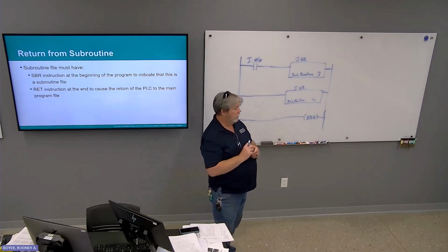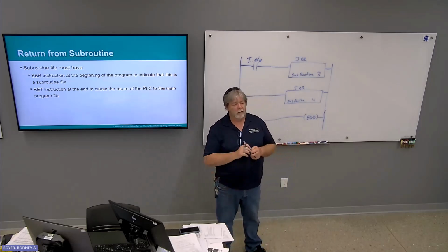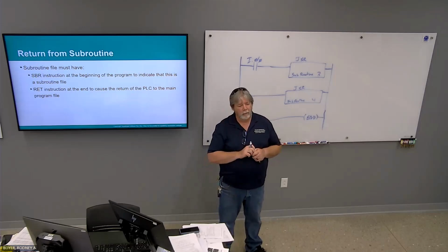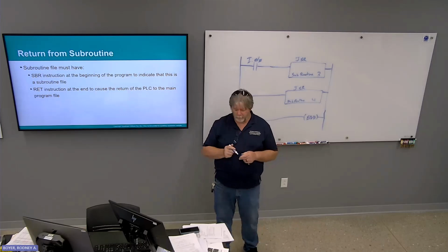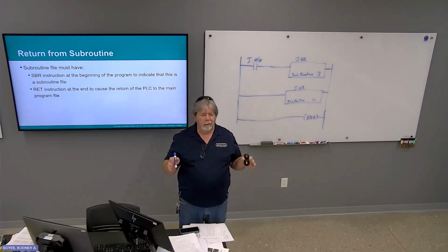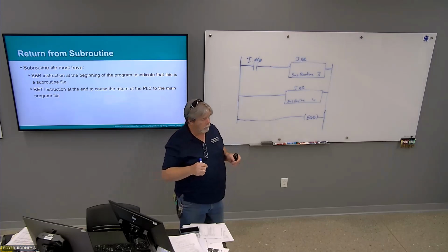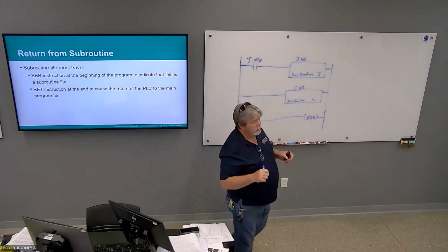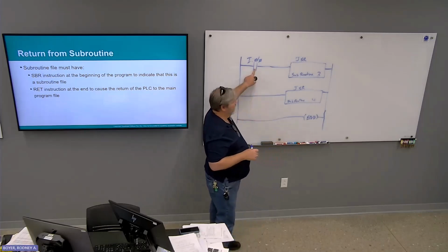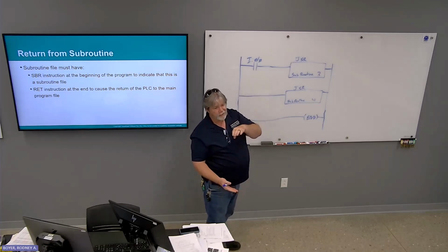One of the cool things about the return instruction, though, is that it does not have to live at the end of your program. So if you need to adjust the pressure inside a vessel of some sort, and you're doing it by modulating valves or controlling fan speed or whatever, when you need to make an adjustment, you turn off your conditional logic in front of the return, so that everything after it also processes.